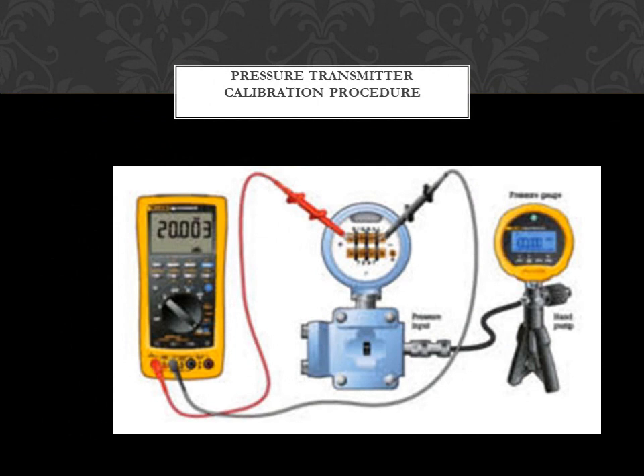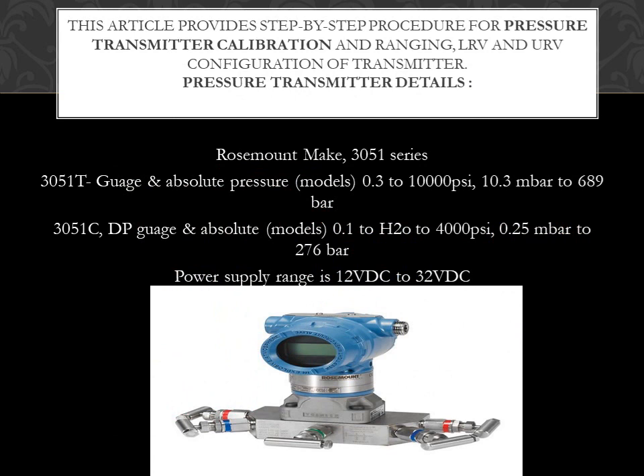As you can see in the figure, pressure transmitter calibration procedure. So we define how to do the calibration procedure in pressure transmitter. These articles provide the step-by-step procedure for the pressure transmitter calibration and ranging, LRV and URV. Configuration of the transmitter, pressure transmitter details.